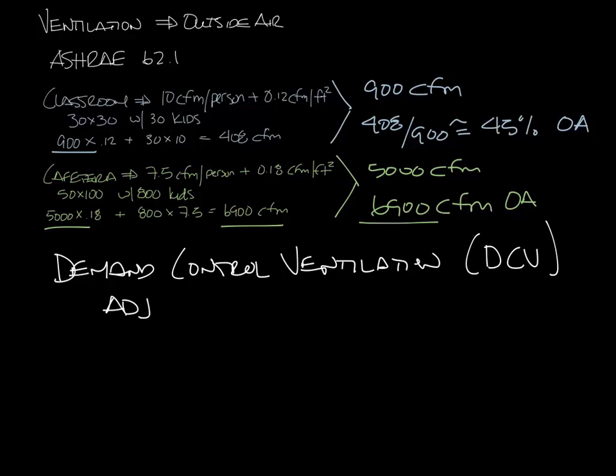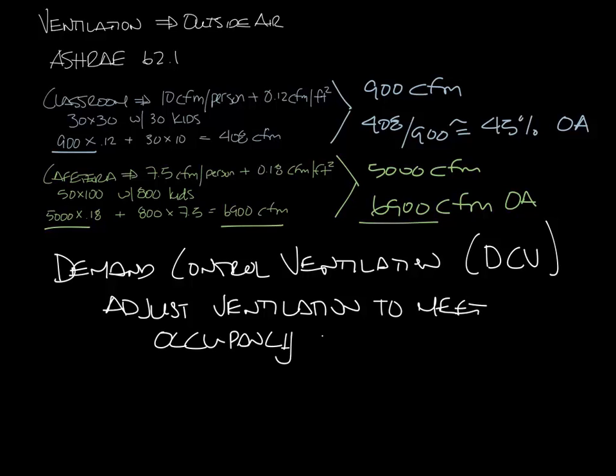Demand control ventilation is adjusting the ventilation air in a space to meet the occupant demand. So in the cafeteria, if there are no occupants, you wouldn't need to bring in the full 6,900 CFM of fresh air. So let's look at why you want to vary the ventilation air based on demand.